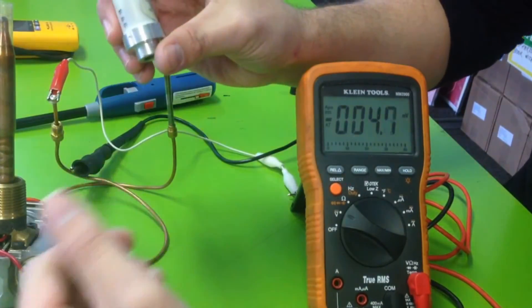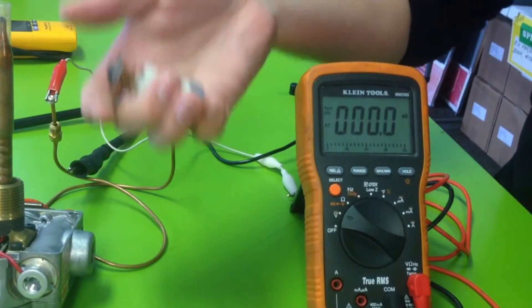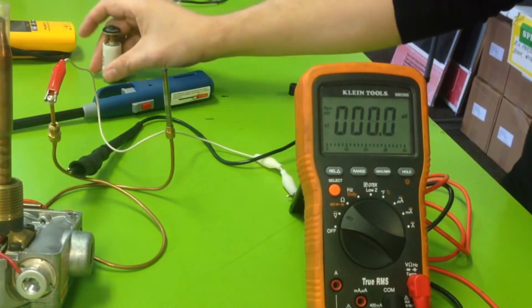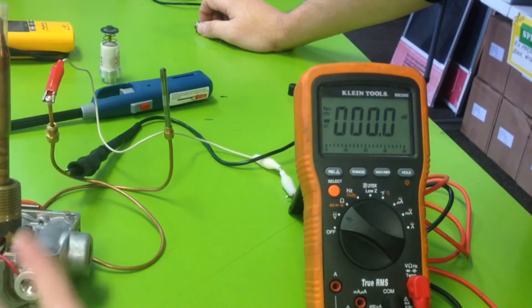Where instead of looking for a millivolt reading, you just simply see if it holds the valve down. That's a more foolproof way of doing it. But the way you do it with the meter - stupid simple. You just hook it up like I just did and you see if it's generating millivolts.